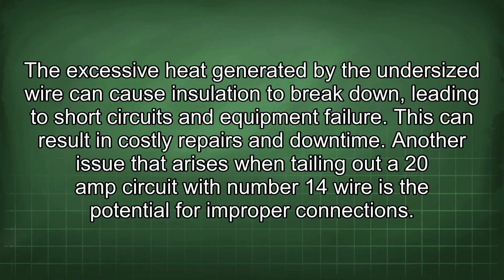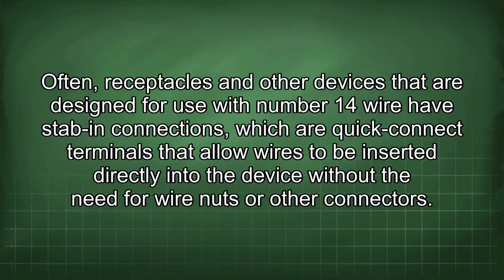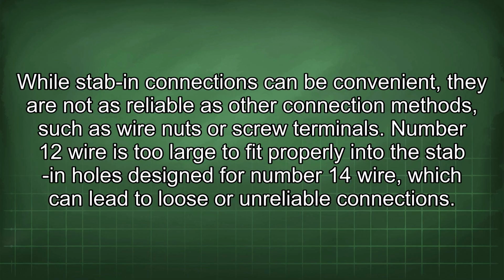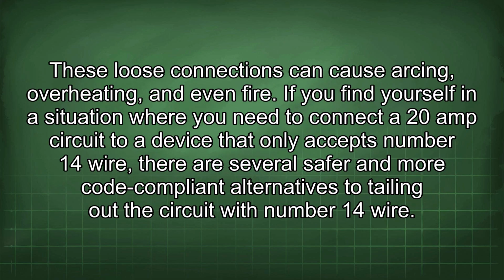Another issue that arises when tailing out a 20 amp circuit with number 14 wire is the potential for improper connections. Often, receptacles and other devices that are designed for use with number 14 wire have stab-in connections, which are quick connect terminals that allow wires to be inserted directly into the device without the need for wire nuts or other connectors. While stab-in connections can be convenient, they are not as reliable as other connection methods, such as wire nuts or screw terminals. Number 12 wire is too large to fit properly into the stab-in holes designed for number 14 wire, which can lead to loose or unreliable connections. These loose connections can cause arcing, overheating, and even fire.